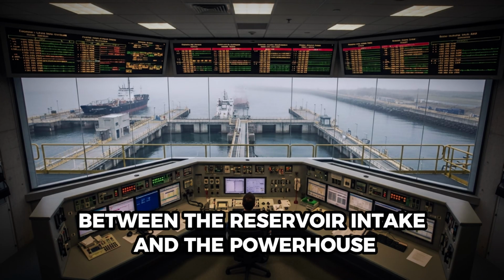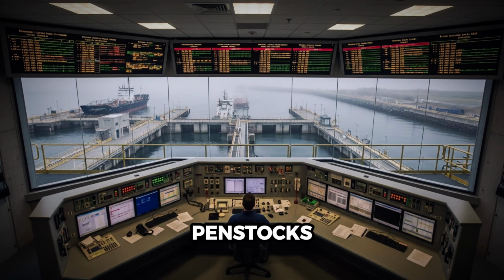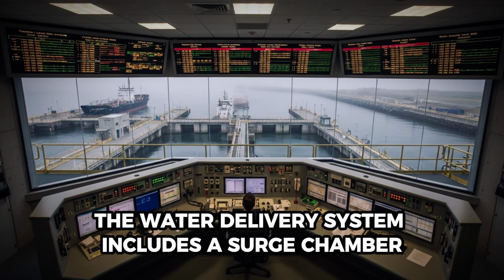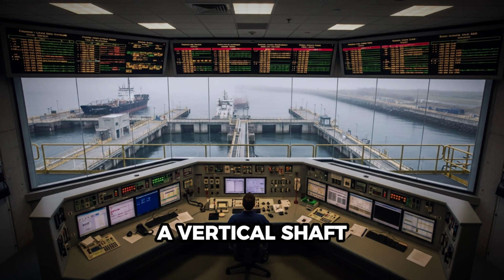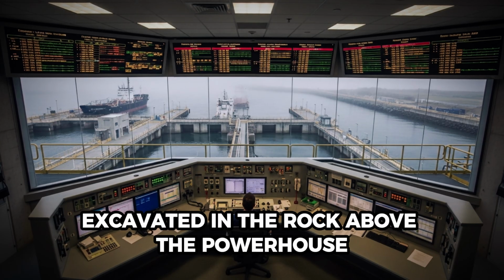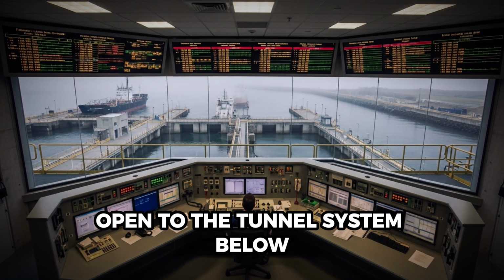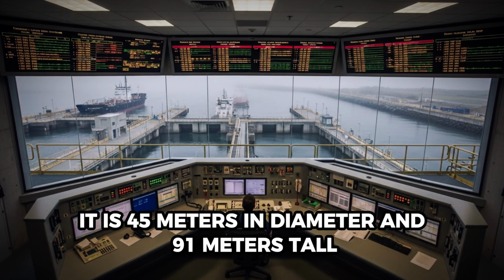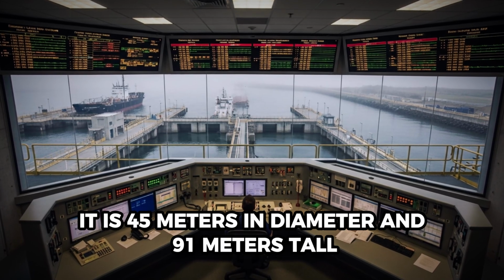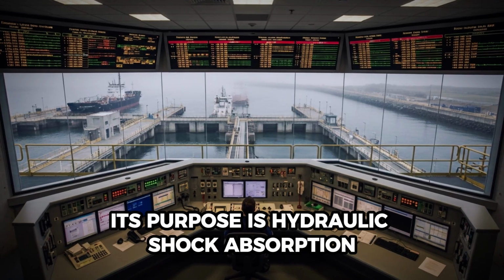9:15 a.m. The surge chamber. Between the reservoir intake and the powerhouse penstocks, the water delivery system includes a surge chamber, a vertical shaft excavated in the rock above the powerhouse, open to the tunnel system below. It is 45 meters in diameter and 91 meters tall. Its purpose is hydraulic shock absorption.